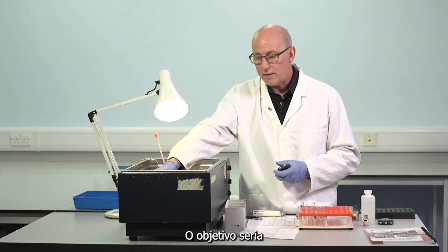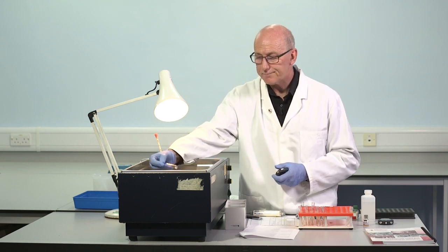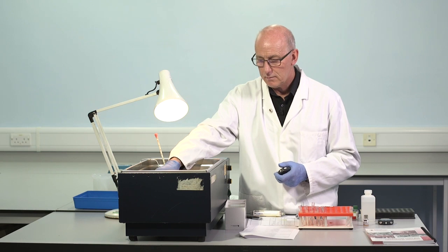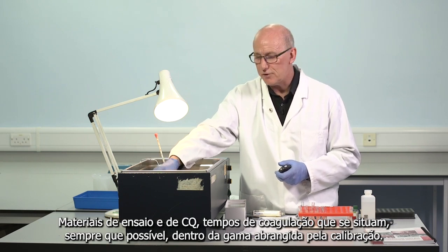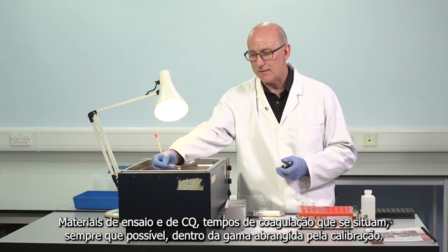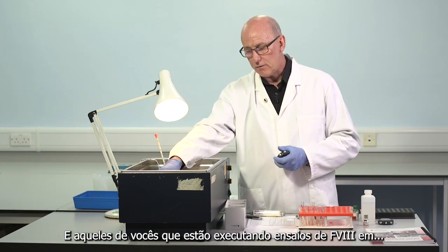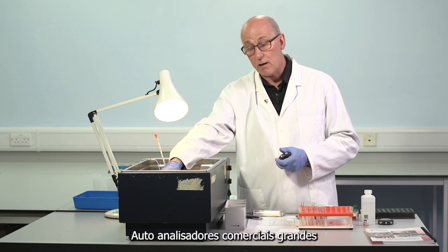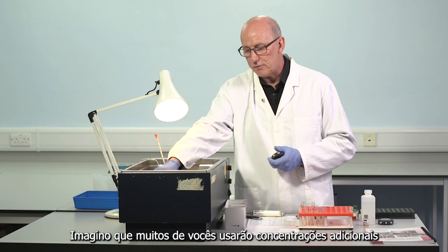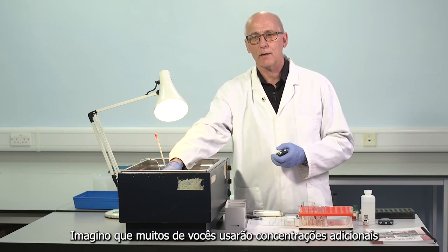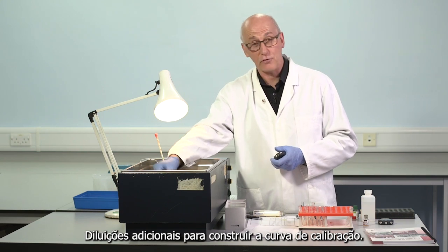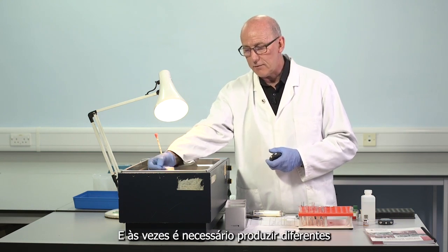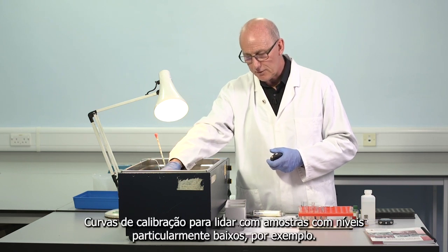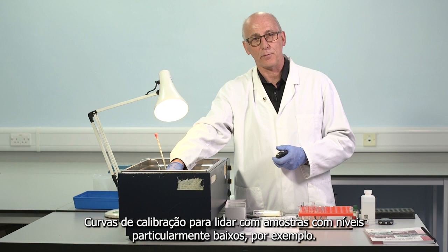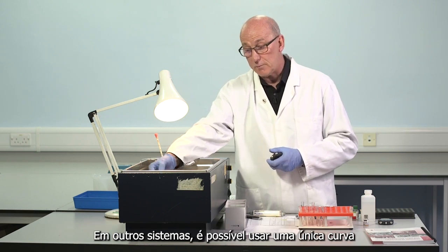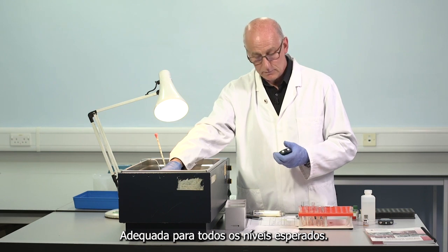So the aim would be to produce, where possible, clotting times on the test and QC materials which sit, where possible, within the range covered by the standard. And those of you who are running factor VIII assays on commercial large autoanalyzers, I imagine many of you will use additional concentrations, additional dilutions to construct the standard curve. And sometimes it's necessary to produce different calibration curves to deal with samples with particularly low levels, for example. On other systems, it is possible to use a single curve that's suitable for all the expected levels.